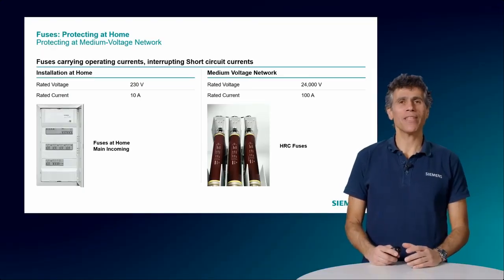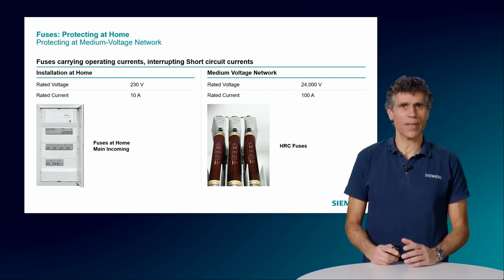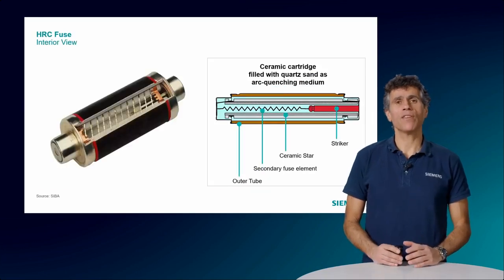We already mentioned them before, as they are used in combination with other devices, usually to perform the task of protecting from short-circuit currents. A fuse is a simple yet effective safety device used to protect electrical circuits from overload or short circuits. It has the disadvantage that it's a one-time device. Once it performs its function, its life ends, and it needs to be replaced. The fuse consists of a metal wire or filament that melts when a current above a defined limit flows through it. When it melts, it breaks the circuit.